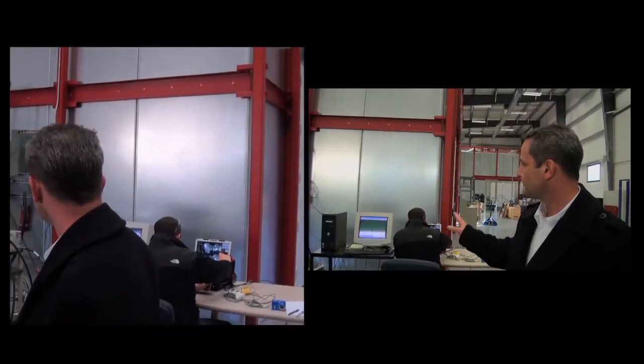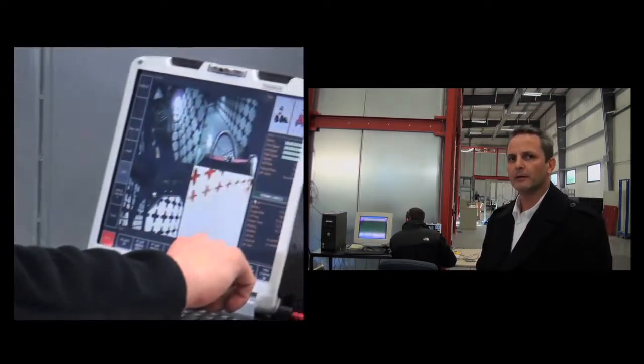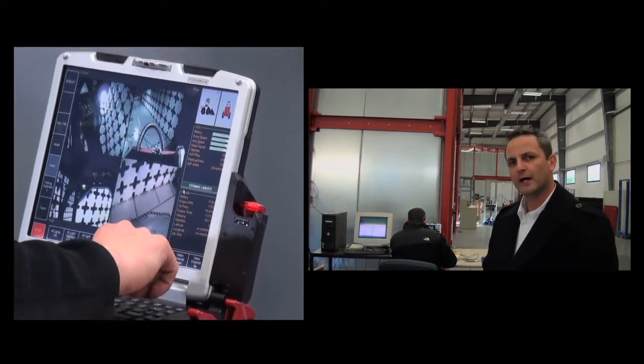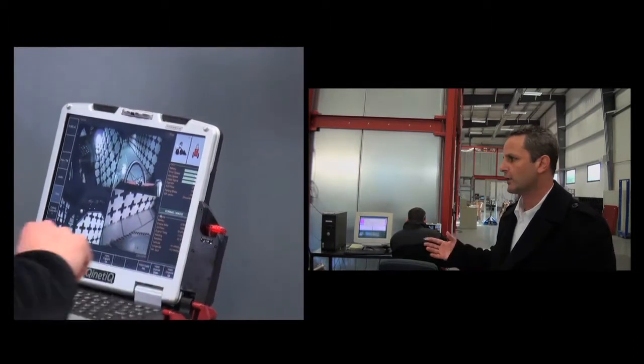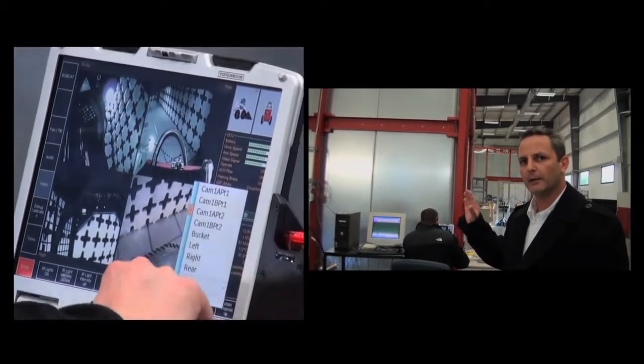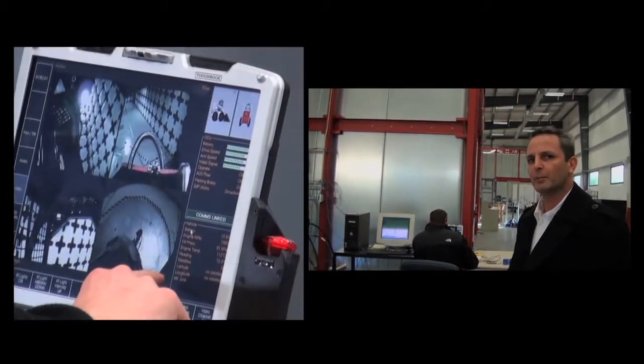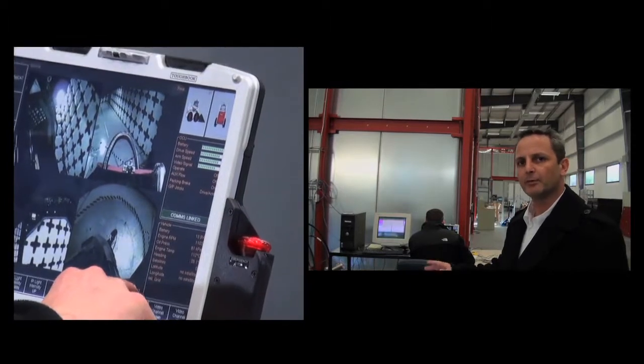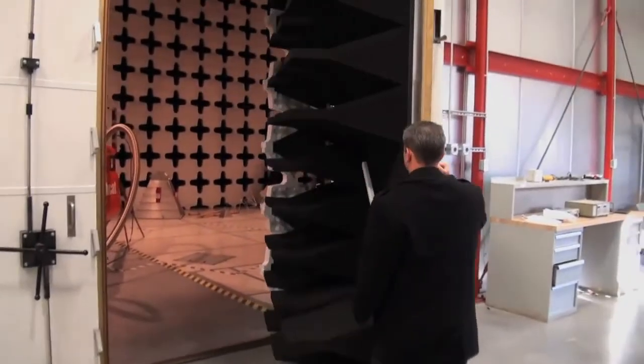As you can see, we're running the test automatically through automation software, our totally integrated lab environment software, commonly known as Tile. Tile is a software program that allows us to control independent pieces of equipment such as signal generators, spectrum analyzers, amplifiers, to perform that test accurately and repeatedly over a period of time. In a minute you'll see we're actually testing a militarized Bobcat used for an application overseas.